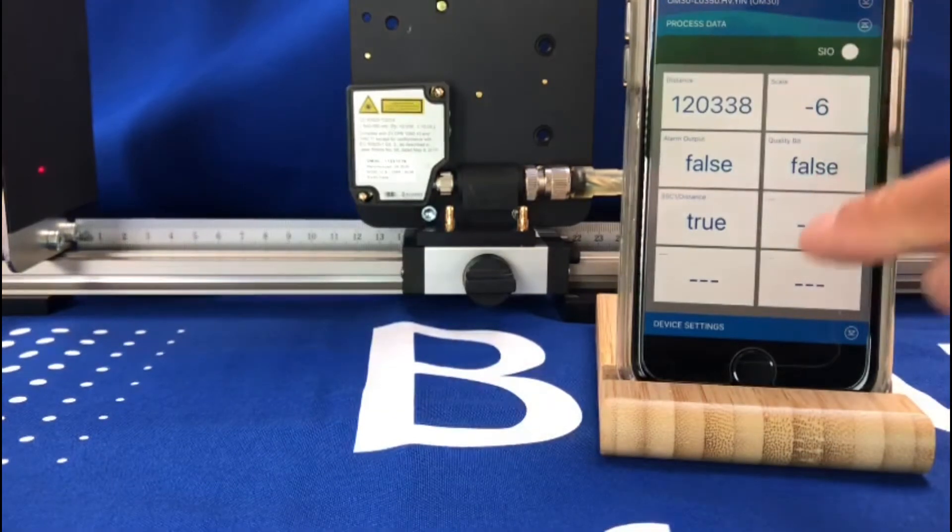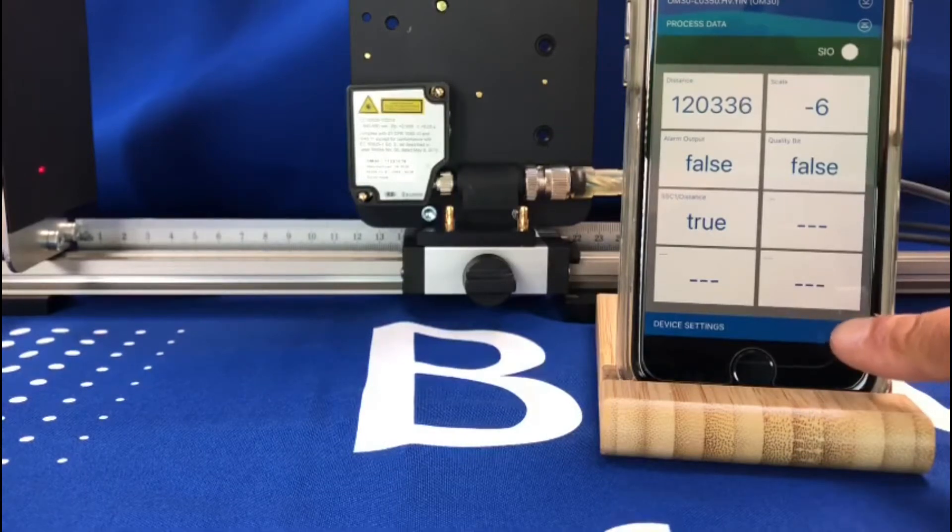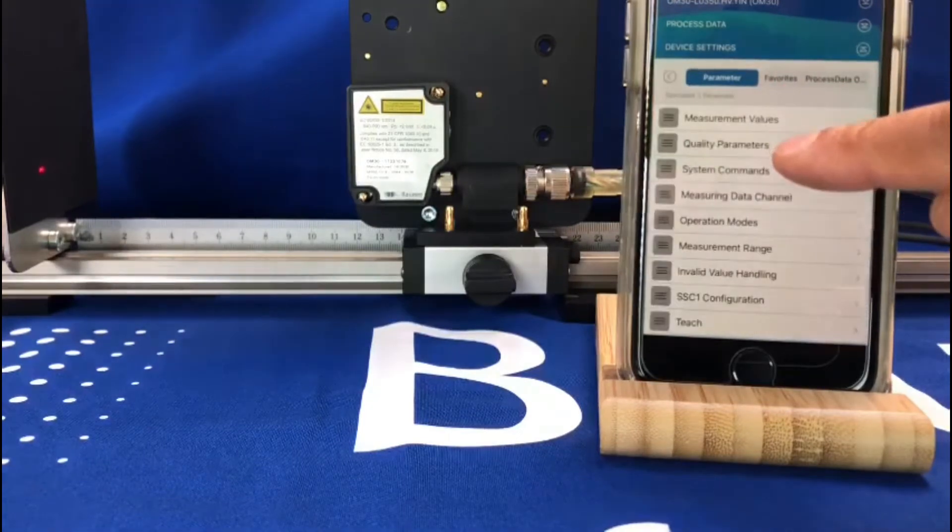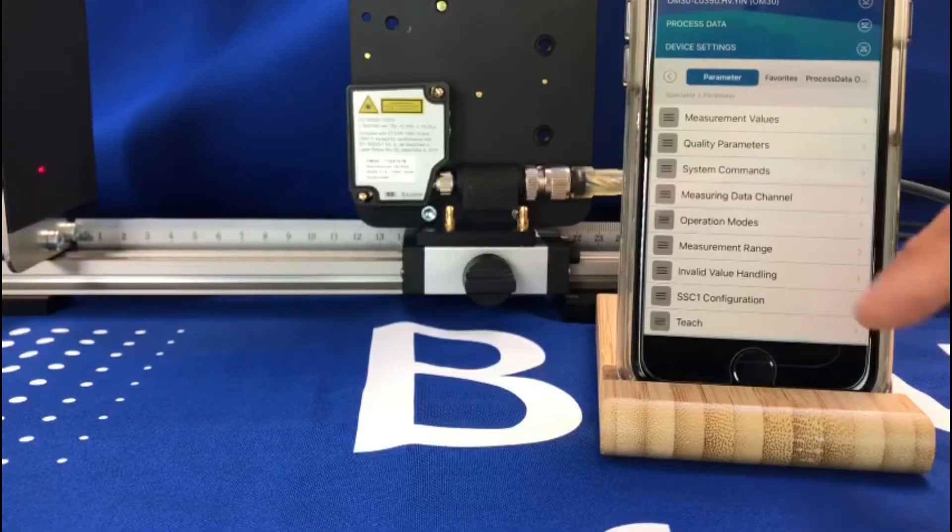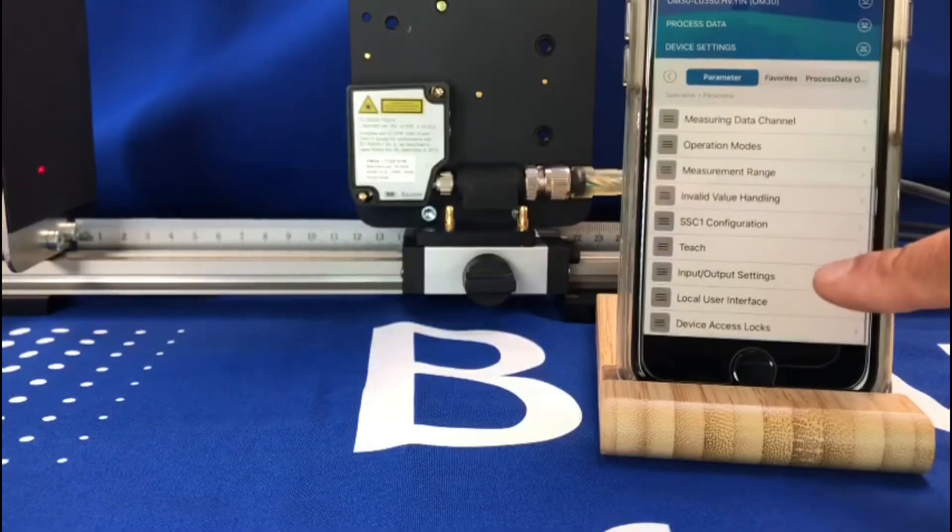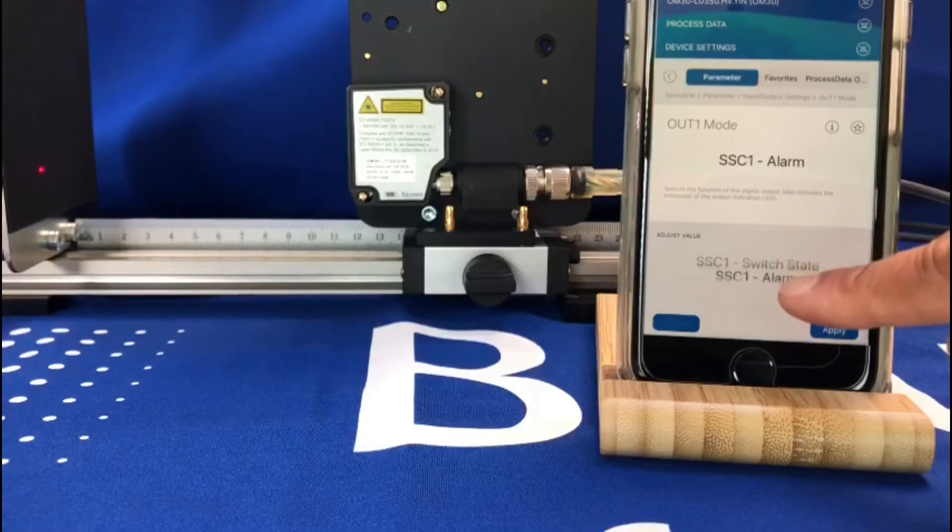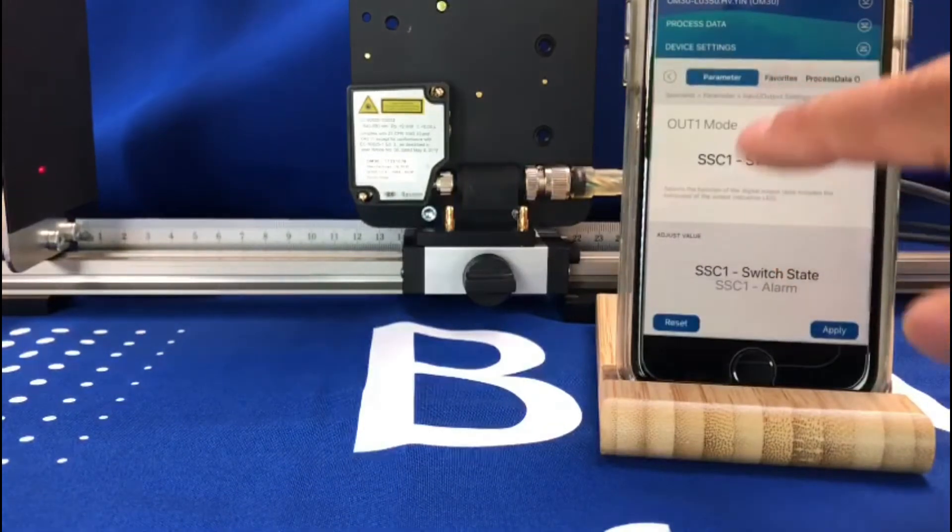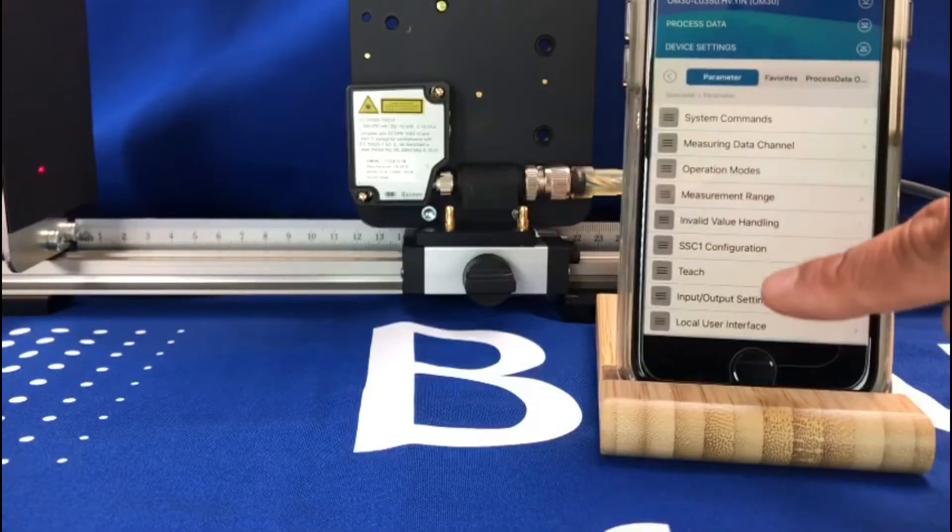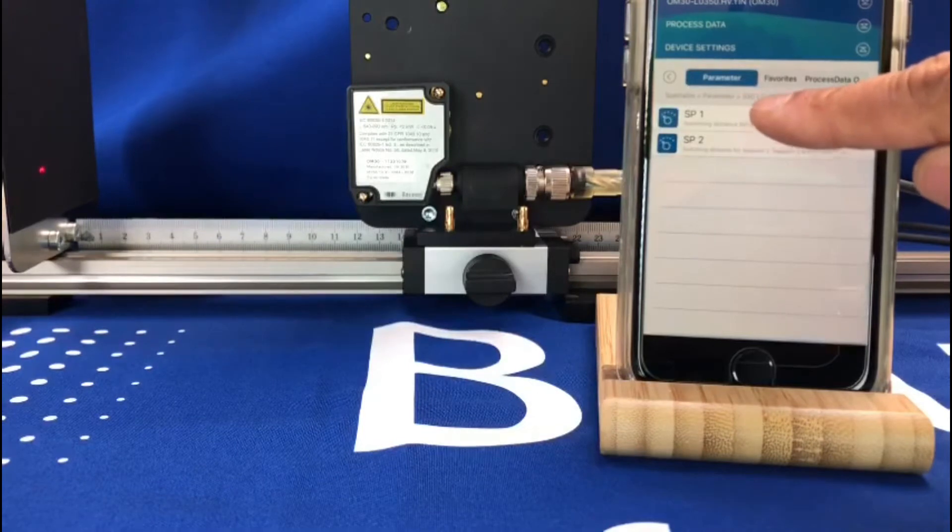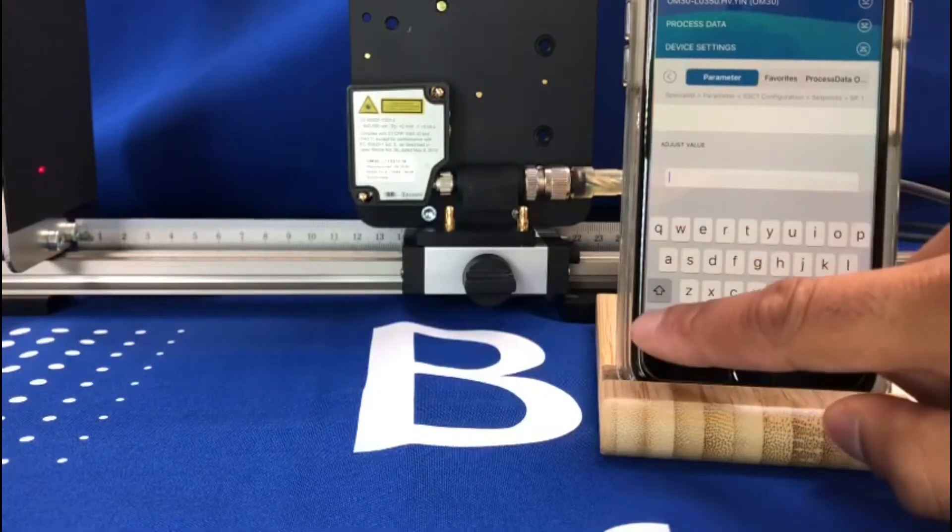So now just to show you how quick and easy it is to set up the sensor via the wireless app. Quickly click on the device settings, going to parameters. For example, if I wanted to set up the physical digital output or assign it to a distance rather than just switching for an alarm, I go to input output settings and change the switch from alarm to switch state, click apply.